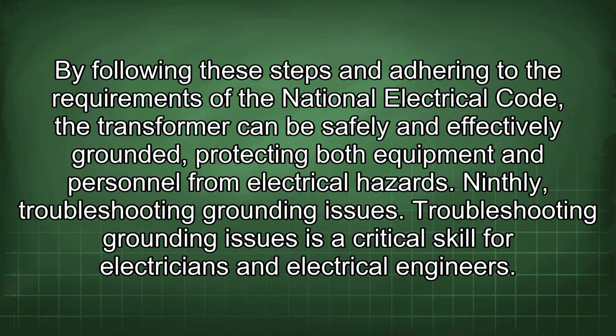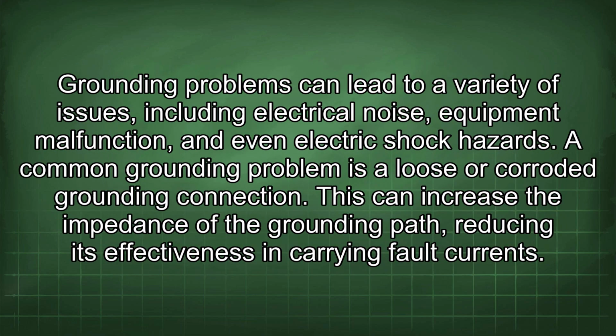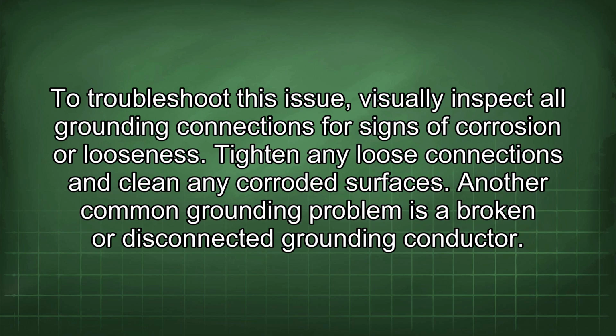Ninthly, troubleshooting grounding issues. Troubleshooting grounding issues is a critical skill for electricians and electrical engineers. Grounding problems can lead to a variety of issues, including electrical noise, equipment malfunction, and even electric shock hazards. A common grounding problem is a loose or corroded grounding connection. This can increase the impedance of the grounding path, reducing its effectiveness in carrying fault currents. To troubleshoot this issue, visually inspect all grounding connections for signs of corrosion or looseness. Tighten any loose connections and clean any corroded surfaces.